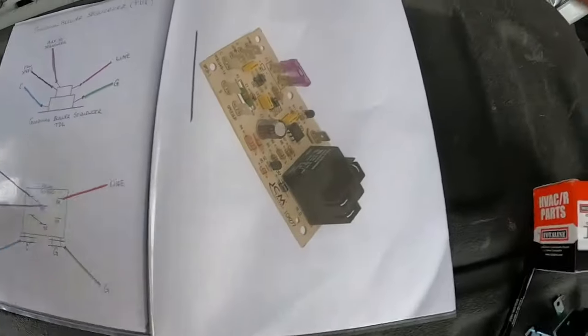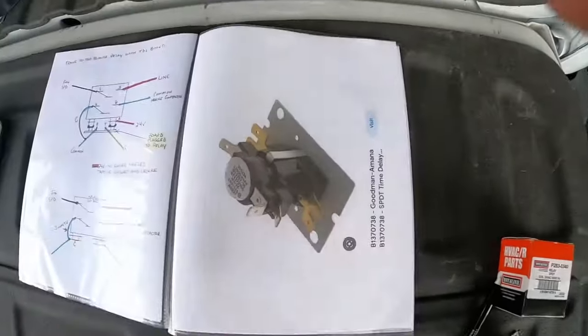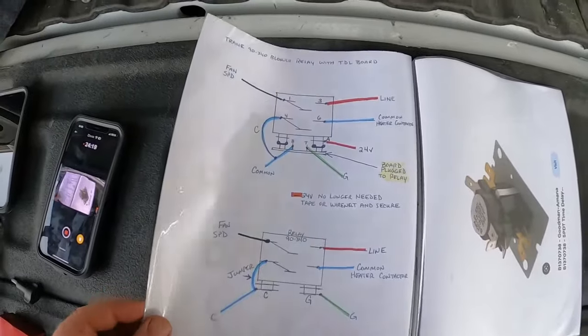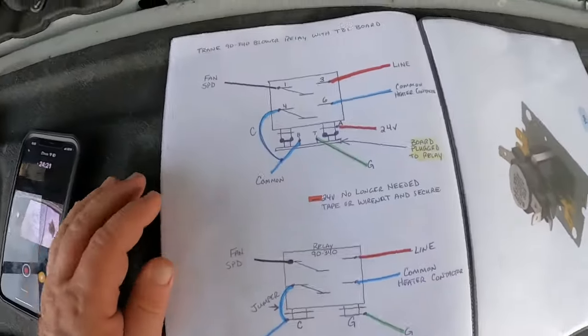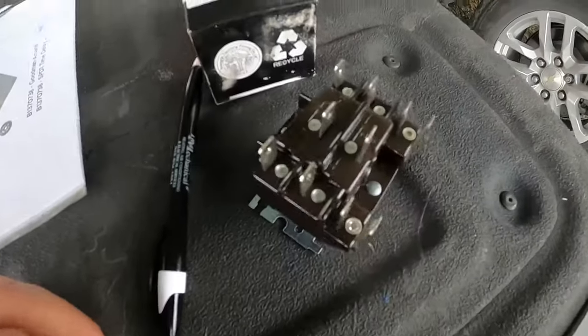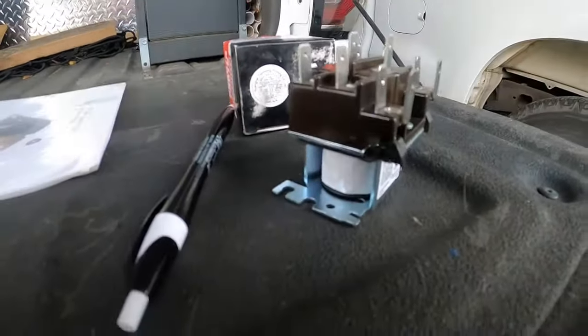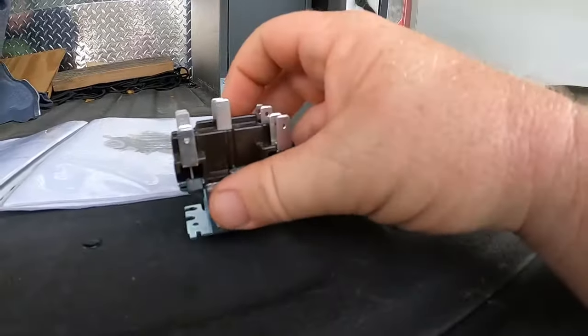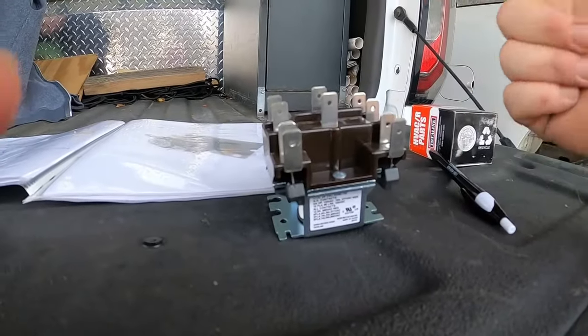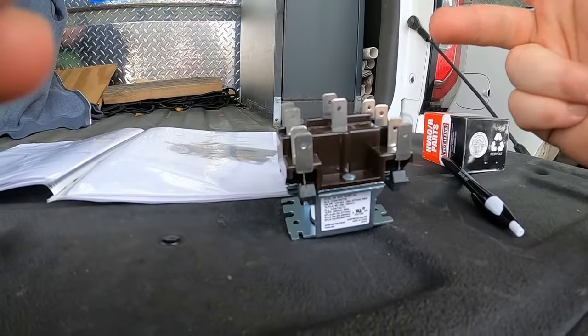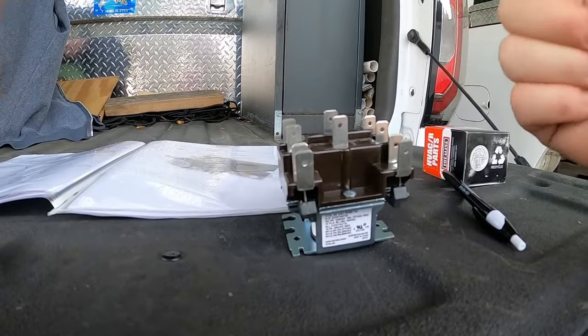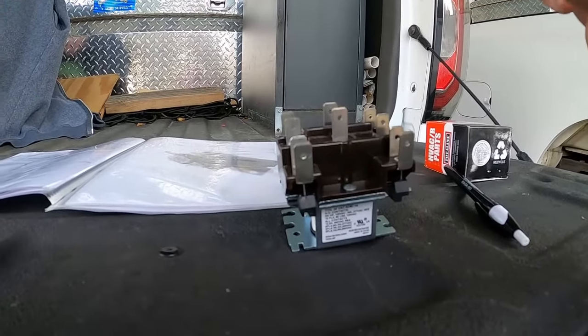So like I said, little things like this I do to try to help the guys out, because they don't teach stuff like this in school. I mean, they show you these boards. Like, I have a board set up at the shop, and it's got the light bulbs on it. I've got one for the blower, one for the heat strips, one for the compressor, one for the condenser fan motor, and I actually do have a reversing valve mounted to the board.